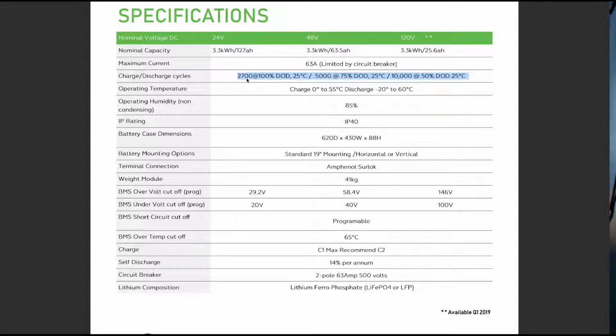So if I'm doing an LFP battery, 22 by 3.3 kilowatt hour battery modules, I'm definitely going to have a lot of parallel battery modules. But the good news is most lithium-ion batteries come with integrated overcurrent protection. Now, don't assume that a semiconductor switch on the front of it is a protection device. It might just turn off the electronics. In the case of the Power Plus Energy batteries, they actually have built into them a circuit breaker.